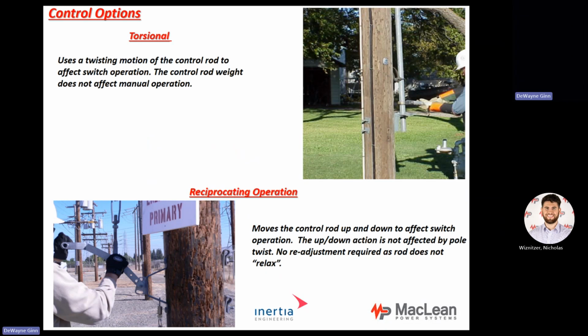Torsional is a twisting motion. If you look to the right there, you see the gentleman is twisting it to open and close the switch. I have high torque value down low where he's at. As I go up the pole, I lose that torque value, and it's called pipe wrap. And as I get higher on the pole to where the switches are, I may have to stage the blades to go into the jaw because they will not enter at the same time with that twisting motion. And that's an adjustment that would have to be made.